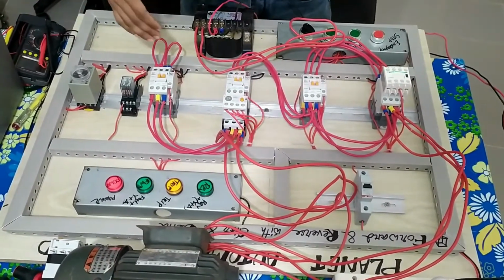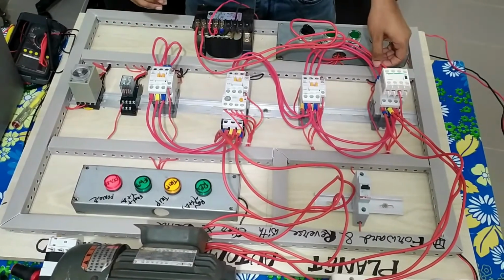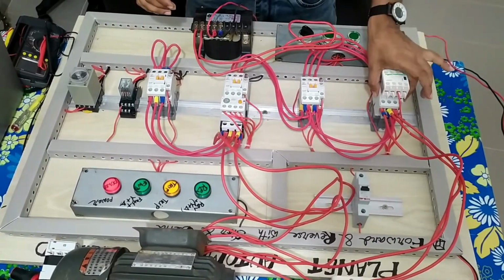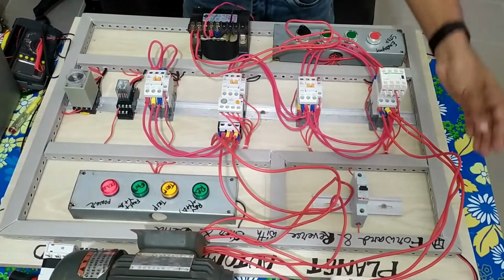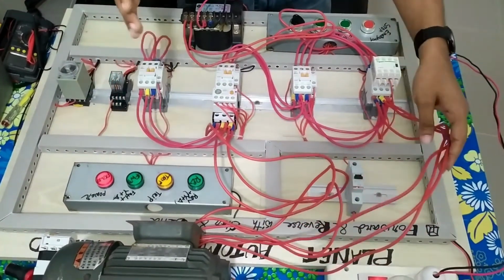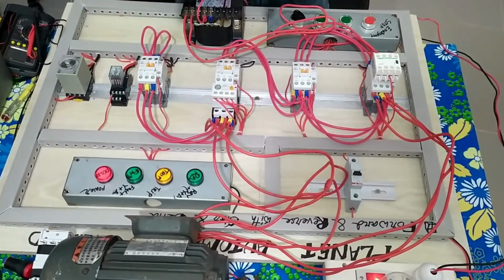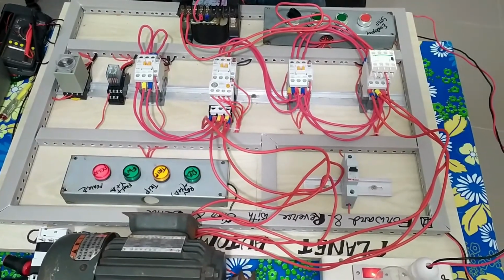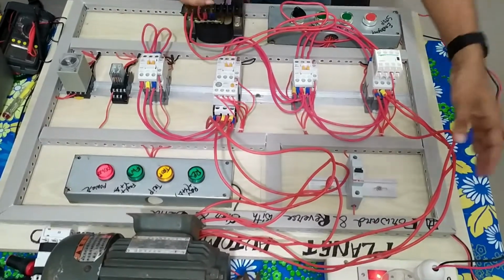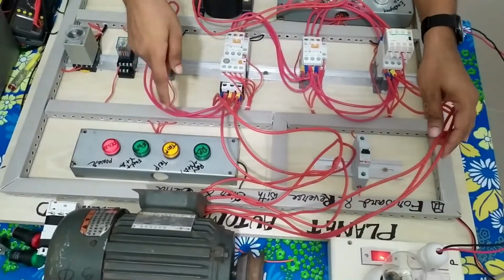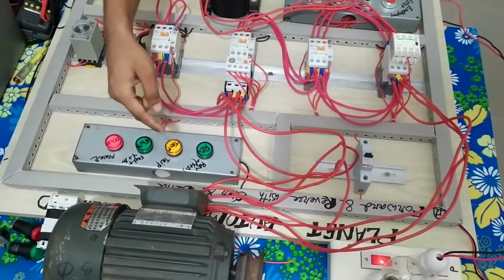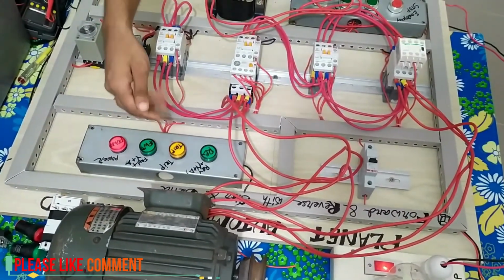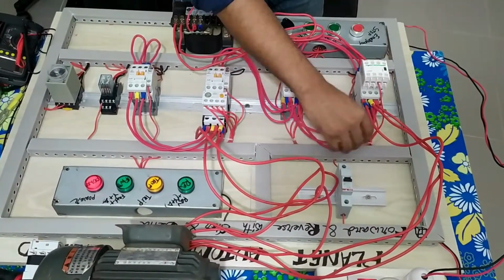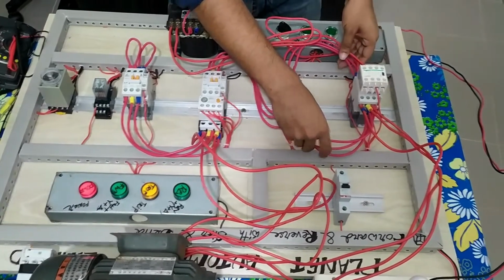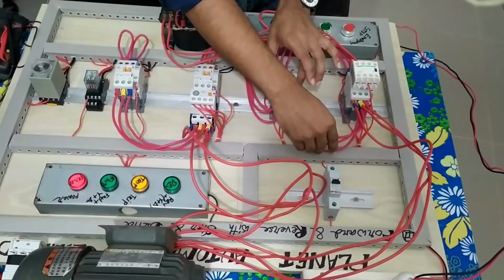This is our input, and its output going to the two phases in our magnetic contactor for forward, going to U1, V1, W1. As I showed in my previous video, the forward line U1, V1 and W1 is directly connected to our terminal input. The three-phase line is directly connected here, and here, and this is our reverse.